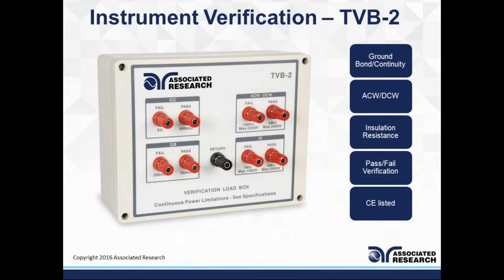Right now we're looking at the TVB2, the test verification box, which is meant to perform verification testing on a ground continuity or ground bond tester, an AC or DC withstand tester, and an insulation resistance tester. As you can see in the picture, there are multiple ports for connecting high voltage or high current outputs from an electrical safety test instrument, a common return point, and a port for pass and fail, with some known resistor values and maximum voltage and current values.